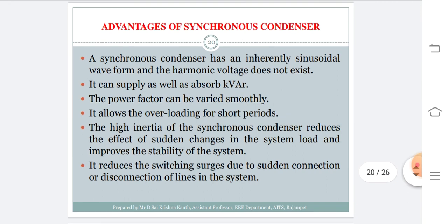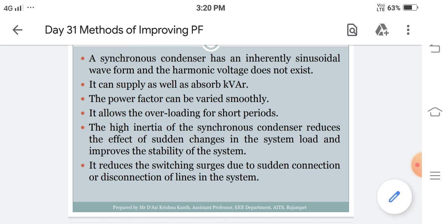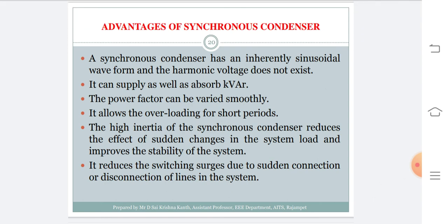Coming to the advantages, it is inherently a sinusoidal waveform and harmonic voltage does not exist. It can supply as well as absorb kVAR. Power factor can be varied smoothly. It allows overloading for short periods. The high inertia of the synchronous condenser reduces the effect of sudden changes in the system load and also improves the stability of the system. It reduces the switching surges due to sudden connection or disconnection of lines in the system.